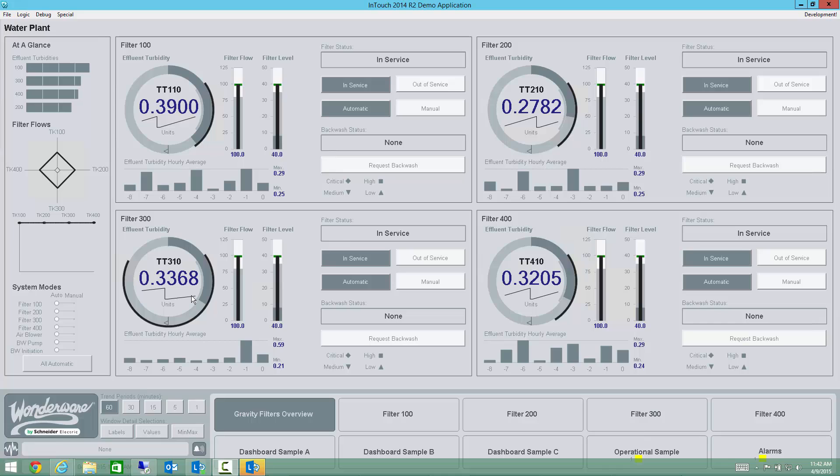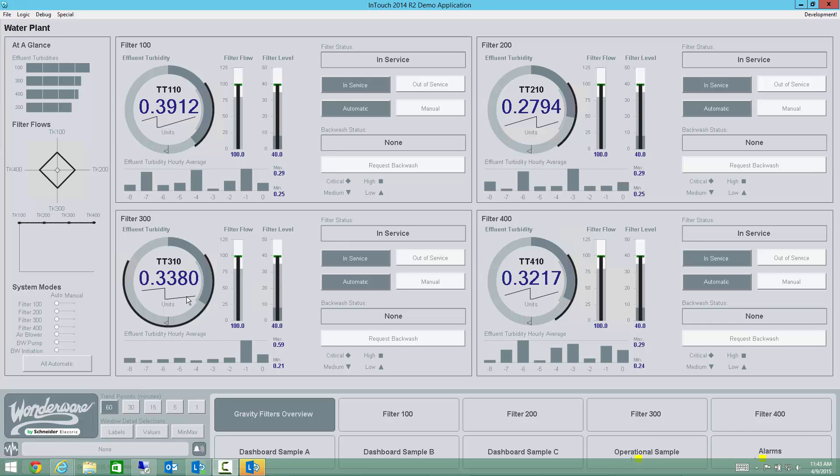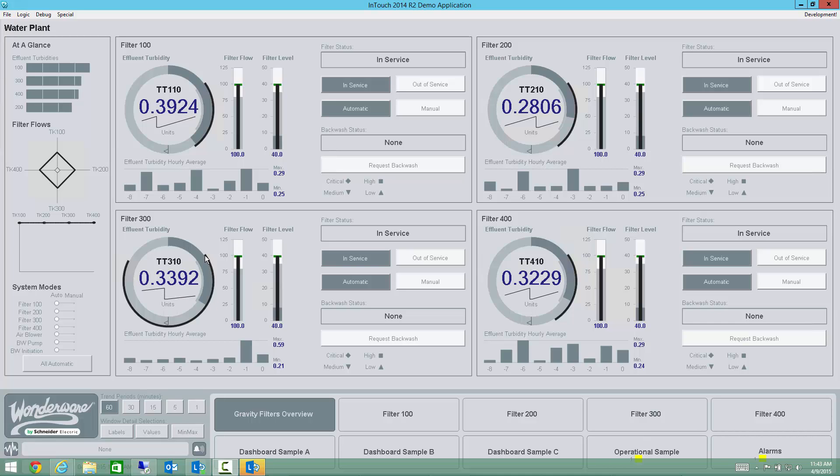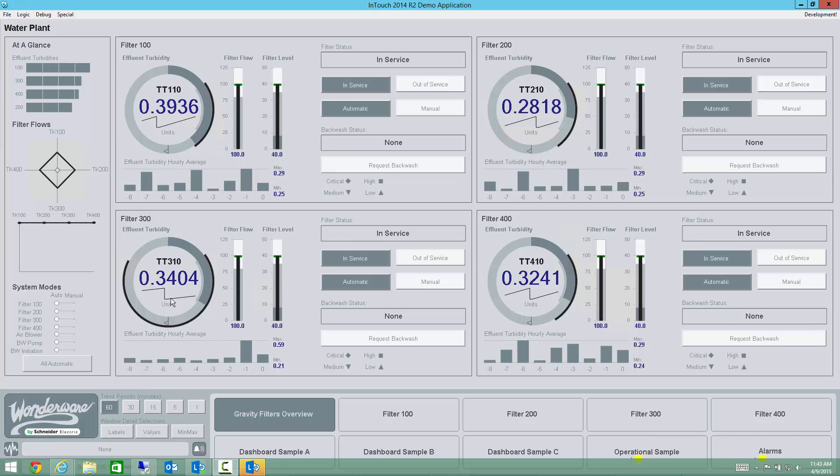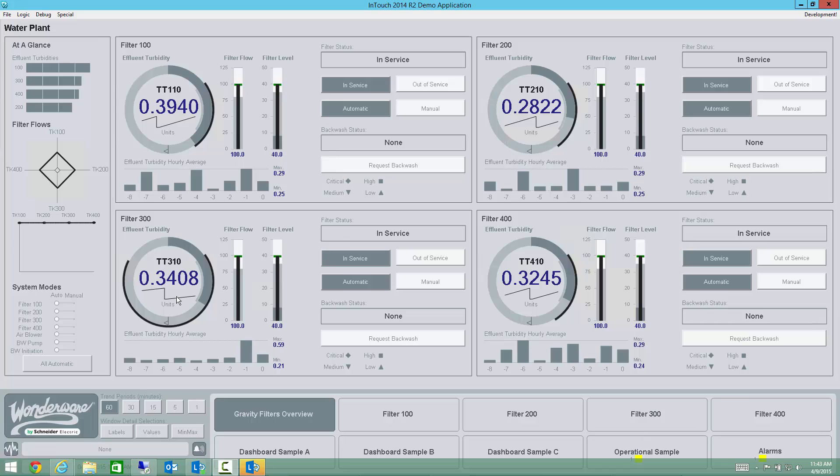I probably would want to go take a look at that. And so the current representation of the value isn't really telling me much in terms of the performance of this unit because it was recently pretty bad, even though right now it's not a problem. So I'd want to investigate that. There's one example of how you can leverage historical data. In this particular case, all the data that's being retrieved for this symbol is coming off of this trend pen. So this trend pen tells me things like the high and the low within that range. And I'm getting the operational limits here from the object on the back end. I'm getting the current value from the object, and the trend itself is coming from historical data on that object. All information that could have been done with a 2014 release, there really was no new capabilities to take advantage of this.